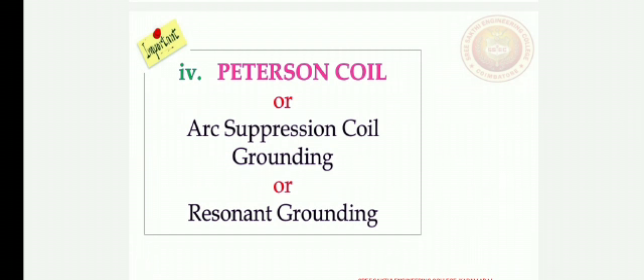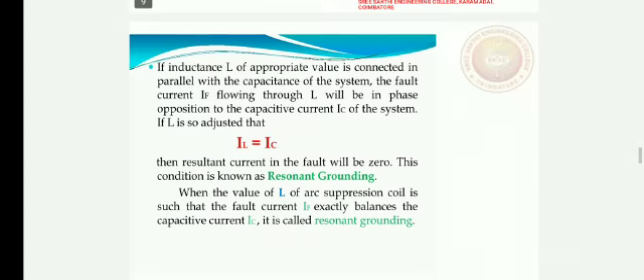Fourth one, Peterson coil or arc suppression coil or resonant grounding. It consists of a coil called Peterson coil or ground fault neutralizer or arc suppression coil whose function is to make arcing earth faults self-extinguishing, and in the case of sustained faults to reduce the earth current to a low value so that the system can supply power with one line earthed. Here IL equals IC, then the resultant current in the fault will be 0. This condition is known as resonant grounding.